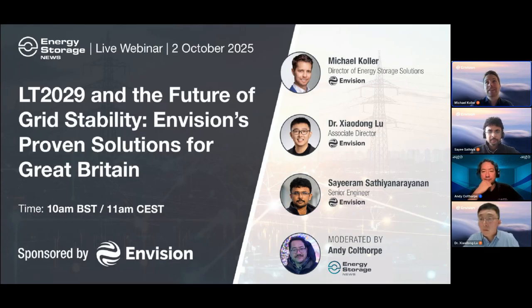So let's start first with overall capability in terms of overload. I think the first thing that needs to be done is sizing, right? It's not that inertia and short circuit level are only done with the overload capability of inverters. Maybe you also want to choose bigger inverter models, and a supplier like us has different sizing options. For example, we have 2.75, 3.45 and 5 MVA PCS that we can potentially use. The overload capability depends on the model, but in our case it's somewhere between 1.2 and 1.5 per unit for these services and the specifications we see in the UK.